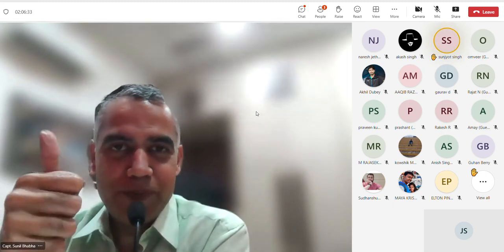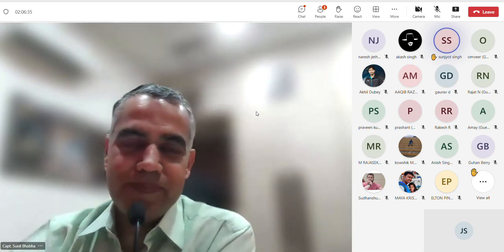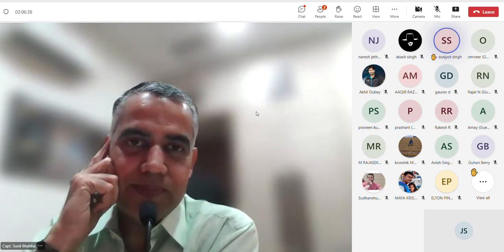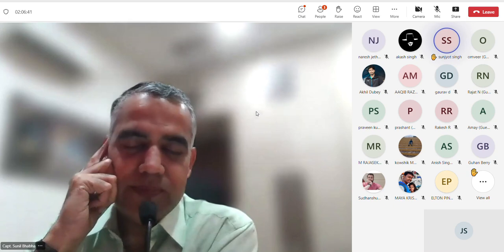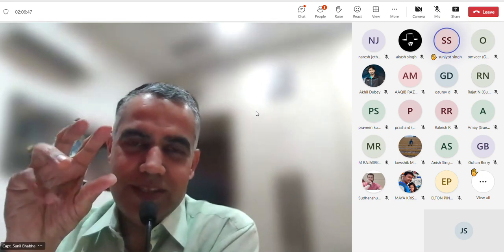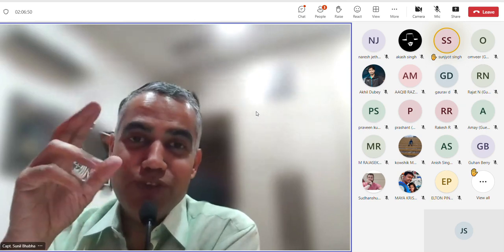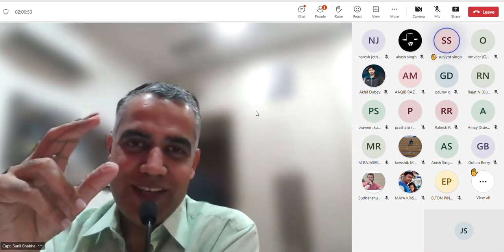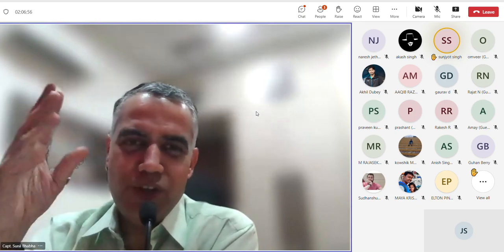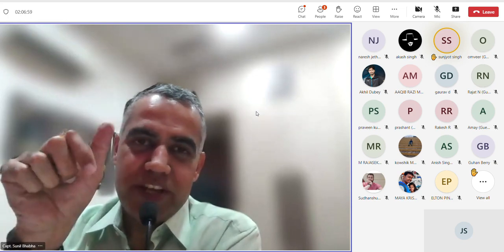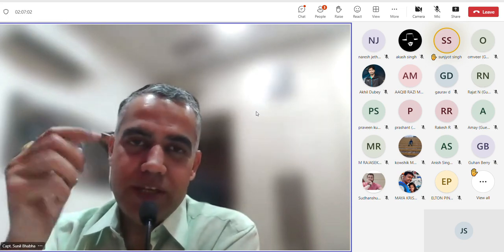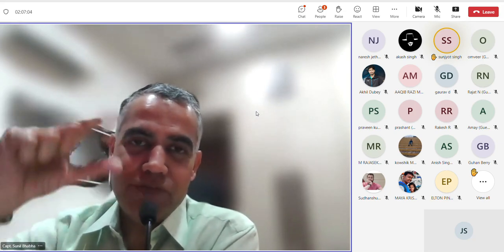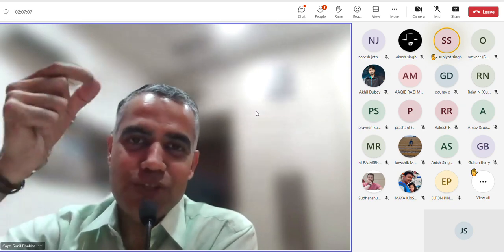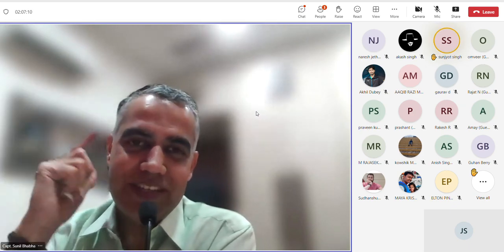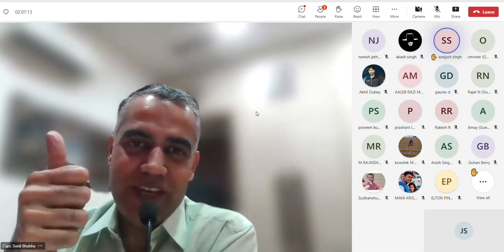Okay. Sir, in case of measuring deeper waters, when the wavelength is more, does the stylus speed also reduce? Because the time taken is more. The stylus speed will reduce when you change the range of the echo sounder, not with the pulse length. The pulse length will automatically keep on changing. When you increase the range, let us say that you make the range double, the same height of the paper now shows double the distance. So the speed of the stylus automatically becomes half. Ah, understood. Okay.